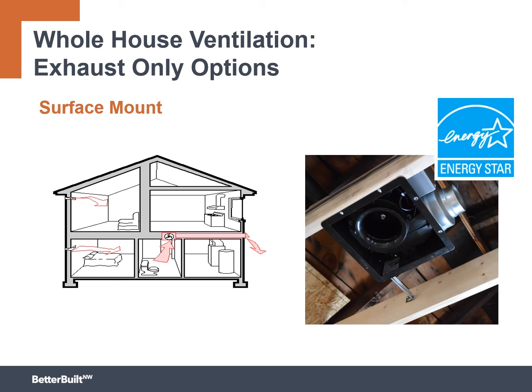Back to Panasonic, they also recommend going to balanced ventilation, even though they sell exhaust fans. They admit really tight homes and really big homes, it makes more sense to do balanced ventilation in those strategies. In really big homes, it's because even though they may be tight, 3 air changes per hour for a big home is still a lot of CFM. So a single exhaust fan may not actually create the negative pressure you wanted to draw air in from the areas you want.